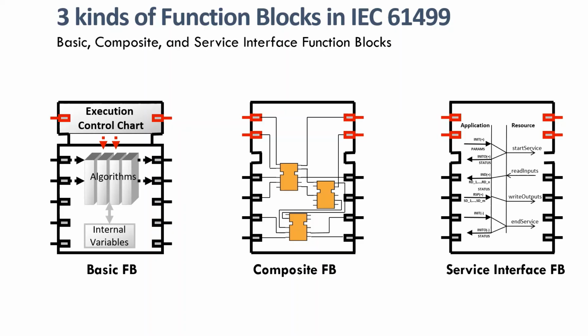Last but not least, there is the service interface function block. Service interface function blocks are intended to be developed by device vendors, so they play the role of device drivers, of hardware interface to different capabilities of hardware. They are not intended to be developed by application developers, but application developers use their services, including service interface function blocks in their programs in order to interact with standardized services of devices.